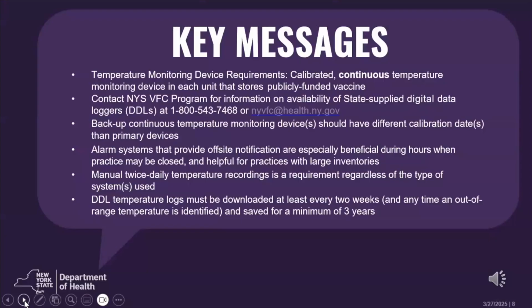The key messages for this training module are: the New York State VFC program requires that providers have a calibrated, continuous temperature monitoring device in each storage unit that holds publicly funded vaccine. Contact the New York State VFC program for more information for the potential of state-supplied devices. VFC providers are also required to have at least one backup continuous temperature monitoring device with a different calibration date than your primary devices. Alarm systems that provide off-site notification may be useful, particularly to practices with large vaccine inventories.